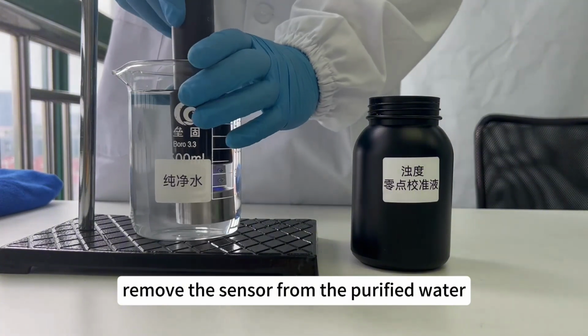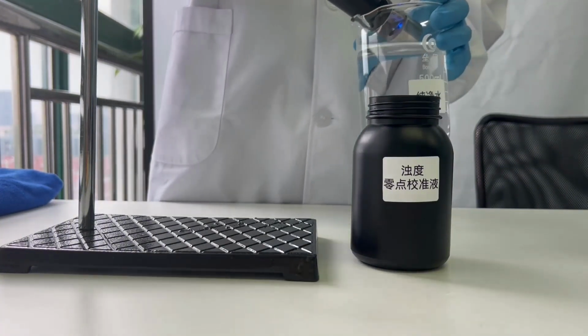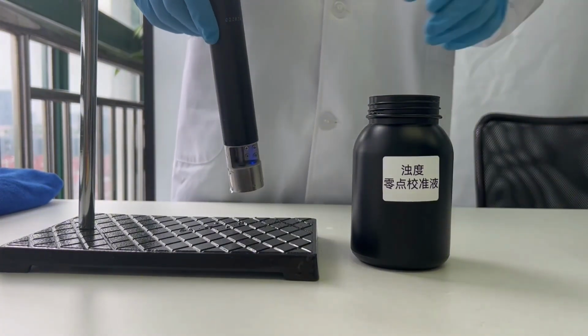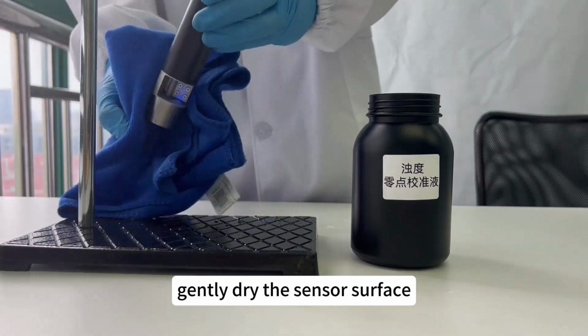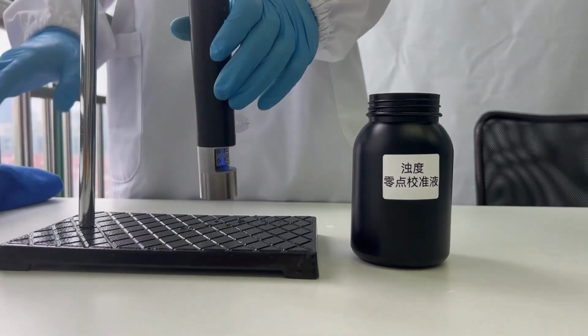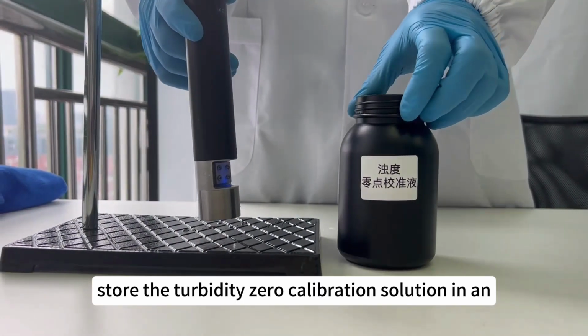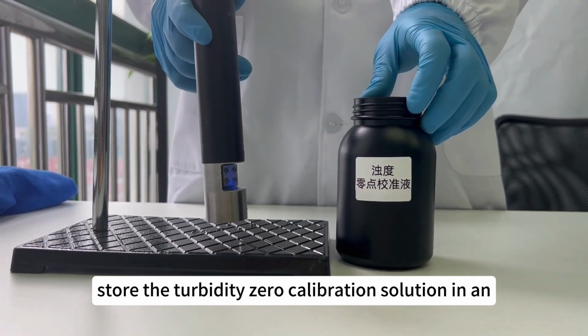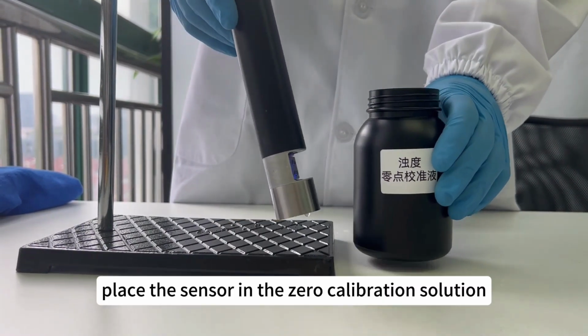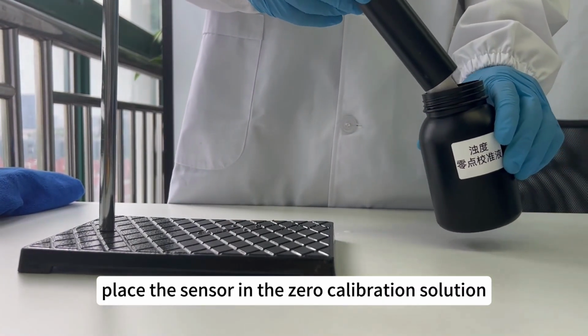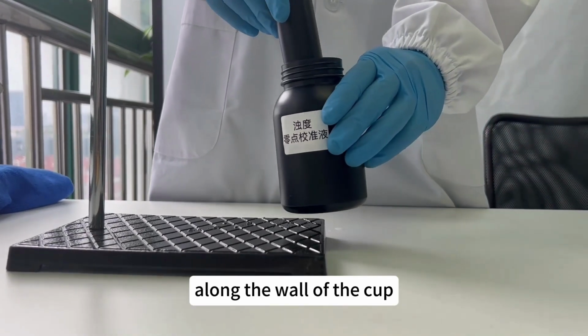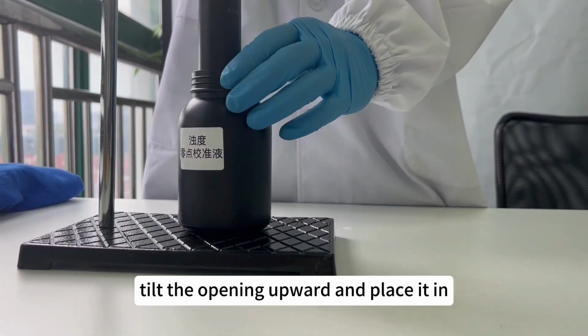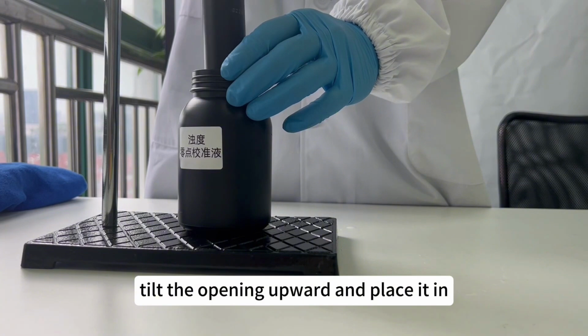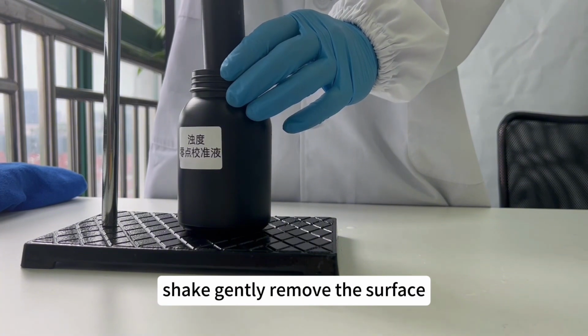Remove the sensor from the purified water. Gently dry the sensor surface. Store the turbidity zero calibration solution in an opaque container. Place the sensor in the zero calibration solution. Along the wall of the cup, tilt the opening upward and place it in. Shake gently. Remove the surface bubbles.